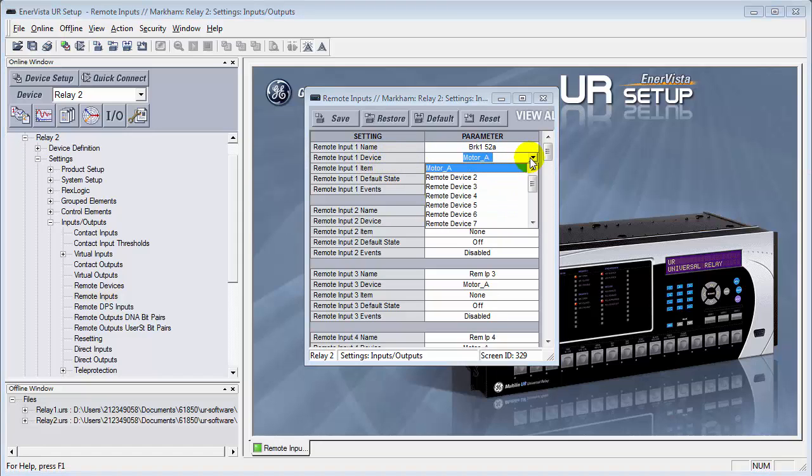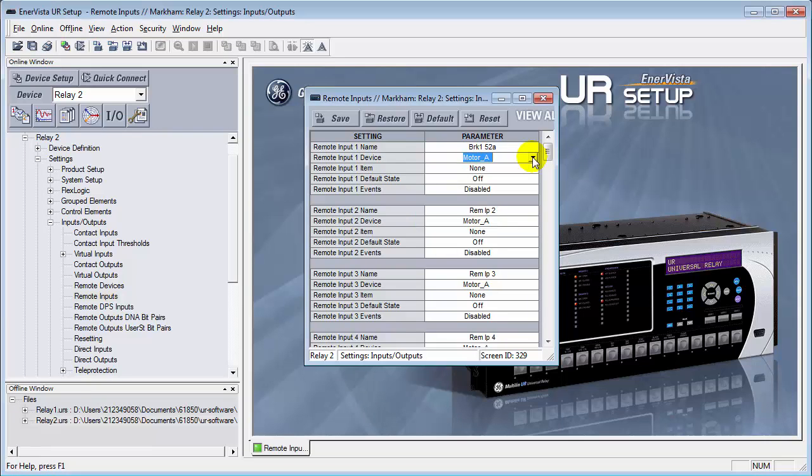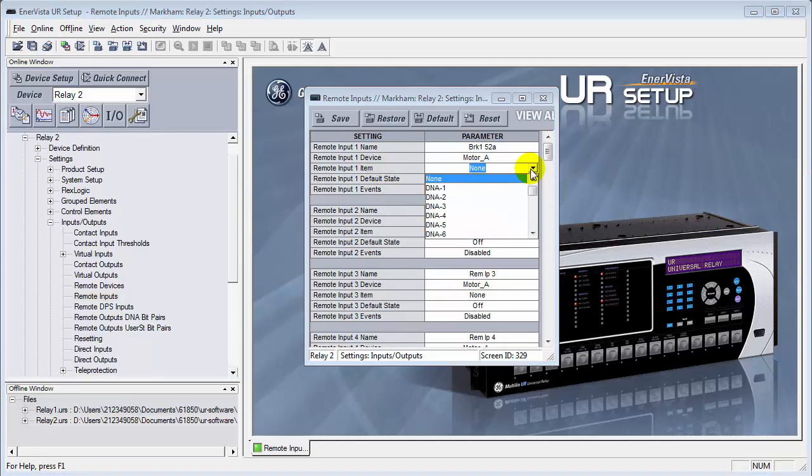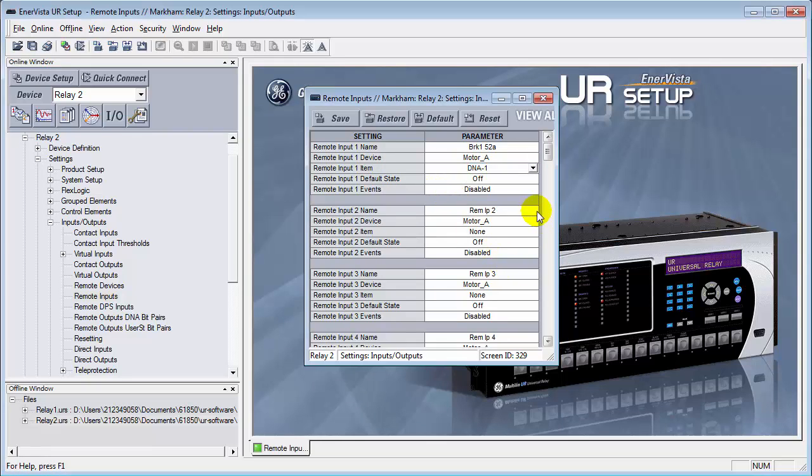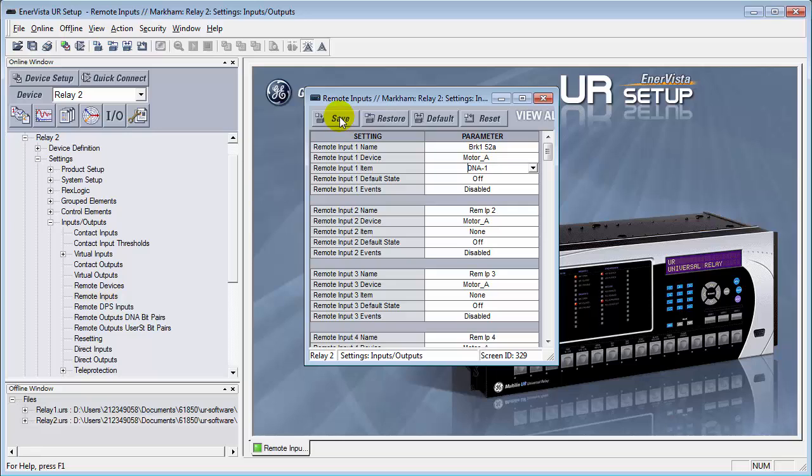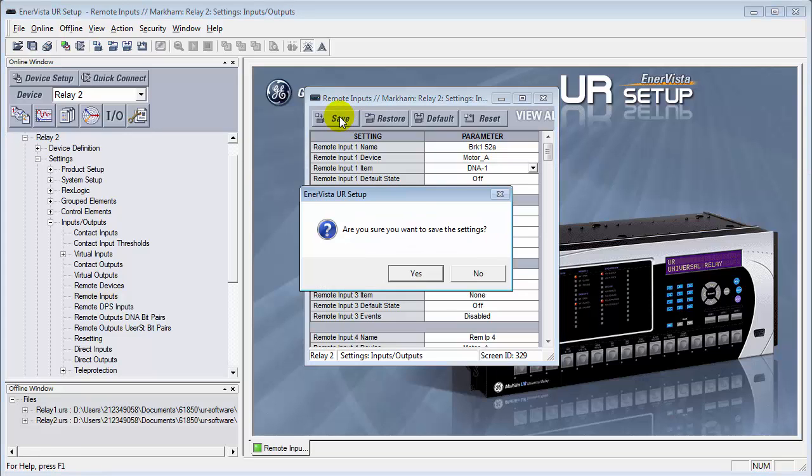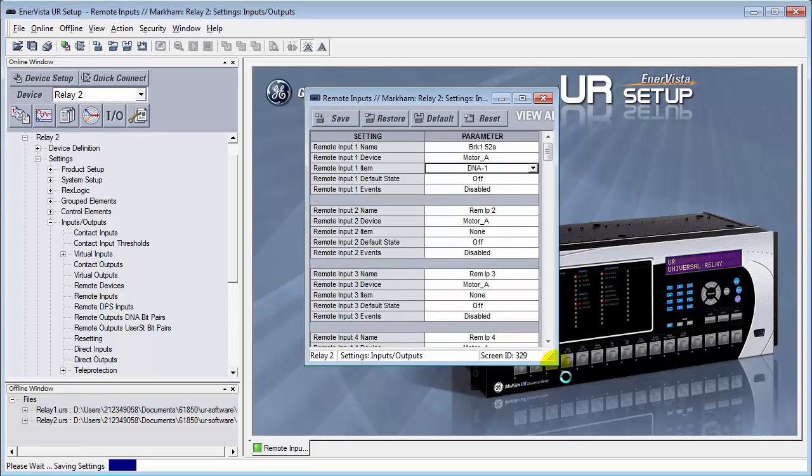In this case, this is motor_a. And under item, we have to select which bit position in that DNA message we're looking for that information. We had selected DNA number one, so we'll place that in there. And the other settings, we'll just leave out their defaults. Save that. Hit yes.